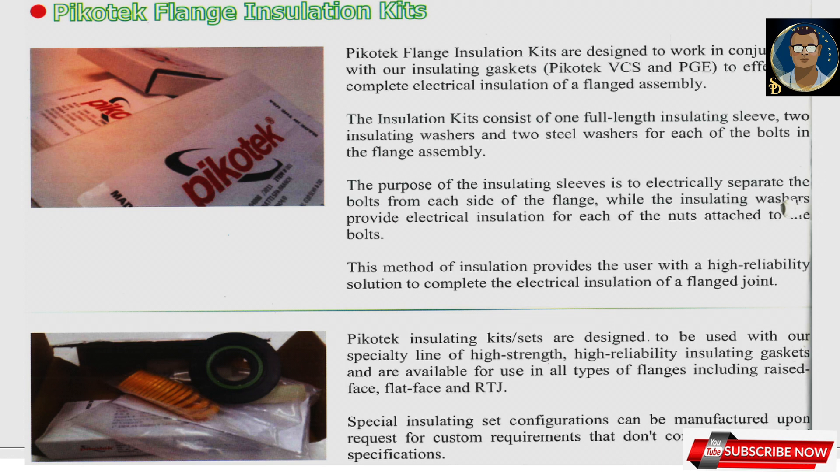The insulation kit consists of one full-length insulation sleeve, two insulating washers, and two steel washers for each of the bolts in the flange assembly. The insulating sleeves electrically separate the bolts from each side of the flange, while the insulating washers provide electrical insulation for each of the nuts. This provides a high-reliability solution for complete electrical insulation of a flange joint. Pikotek insulation kits are available for all types of flanges including raised face, flat face, and RTJ. Custom configurations can be manufactured upon request.